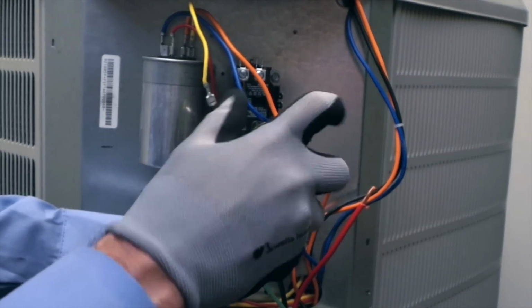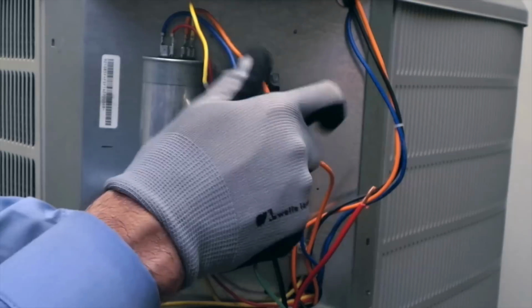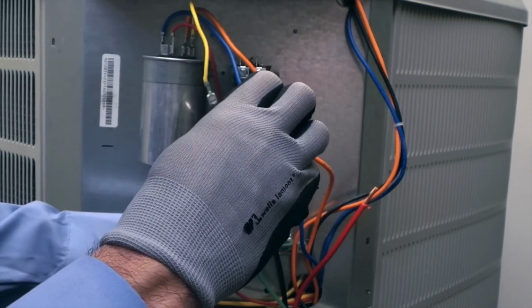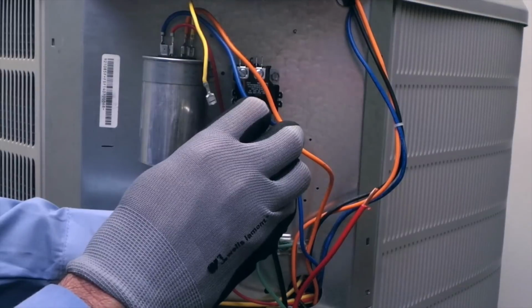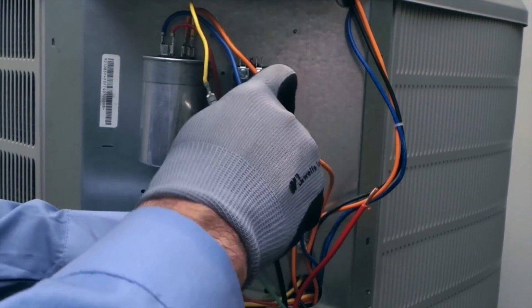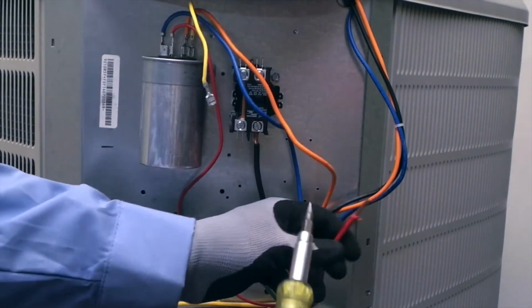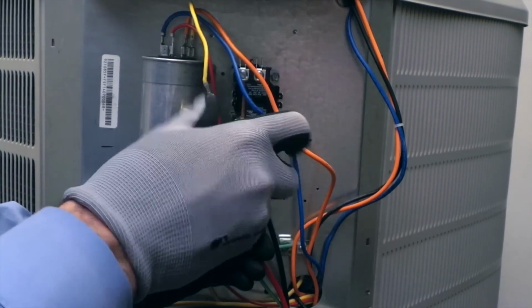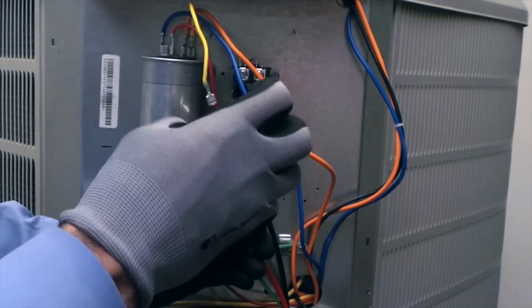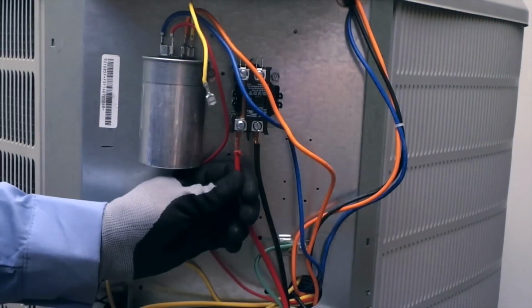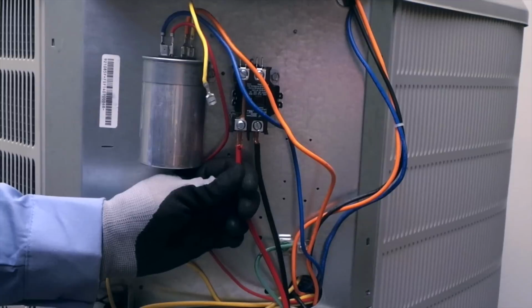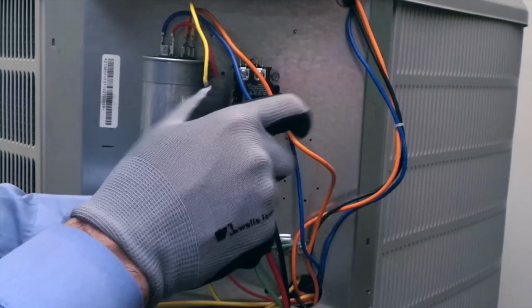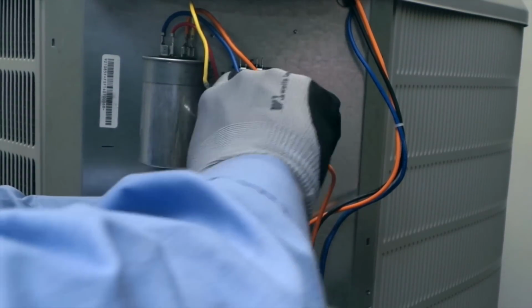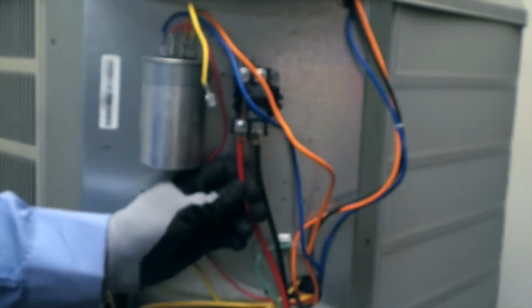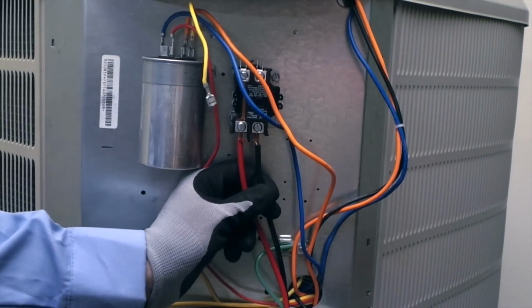Now let's hook up our supply voltage wires to the bottom or line side of our contactor. We start with our black wire, putting it into the lug at the bottom of the contactor, making sure that it's nice and tight. And now we will insert the red wire, also coming from our disconnect box, supply voltage, to the line side of our contactor. When inserting our wires into the lugs, we want to make sure that all the wires go into the lug and that we have no frays that could cause shorts or loose connections. Make sure all of our wires are tight and secure.